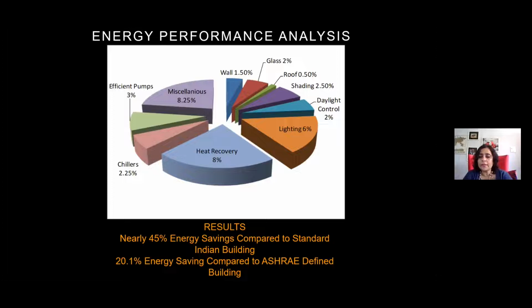Using the right kind of lighting, having natural light most of the time through shading systems, and also having perimeter lights linked to daylight sensors, we were able to save almost 20% energy over the ASHRAE-based defined case and 45% energy compared to a standard Indian building.